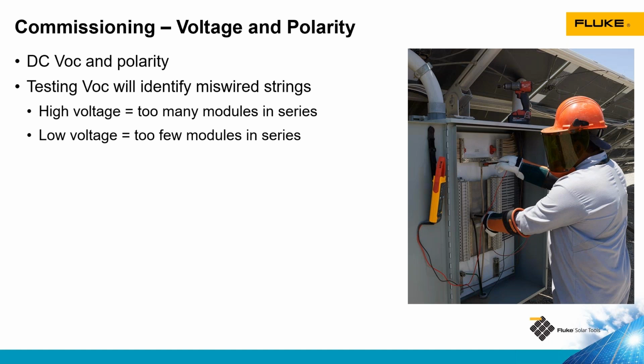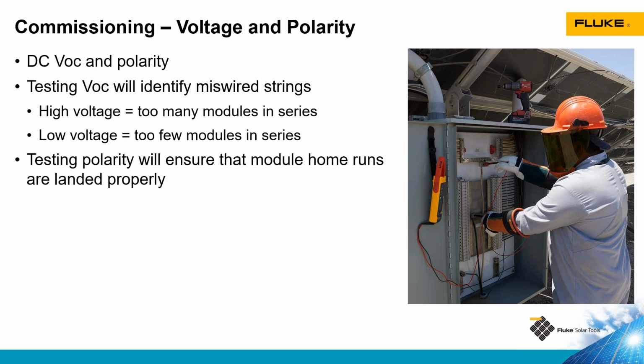If we get voltage that's too high, it's often a result of too many modules being wired in the circuit. If we have voltage that's too low, we have too few modules. And usually these are paired together, where someone put too many modules in one string and not enough in another string. Now, testing polarity is making sure that our positive conductors are all connected to the positives and our negatives are connected to negatives and nothing got accidentally switched.